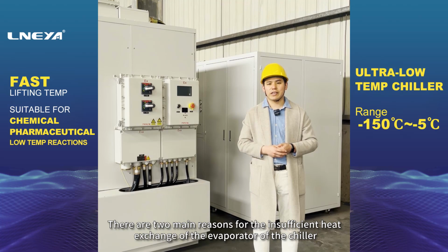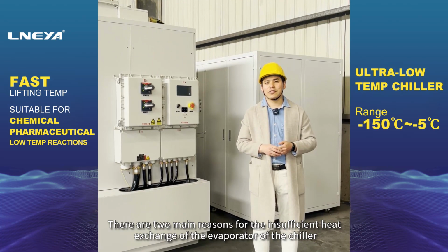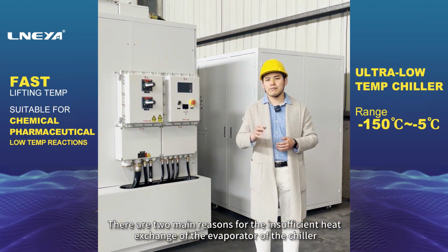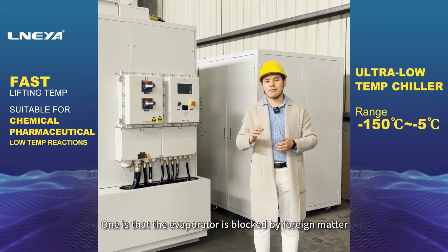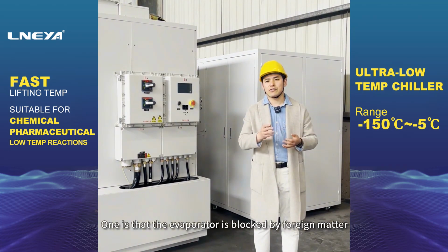Insufficient heat exchange of the evaporator. There are two main reasons for the insufficient heat exchange of the evaporator of the chiller. One is that the evaporator is blocked by foreign matter.